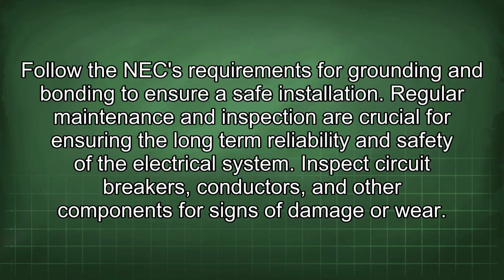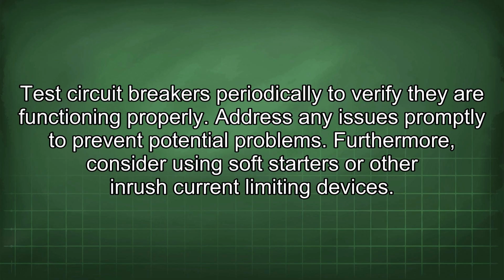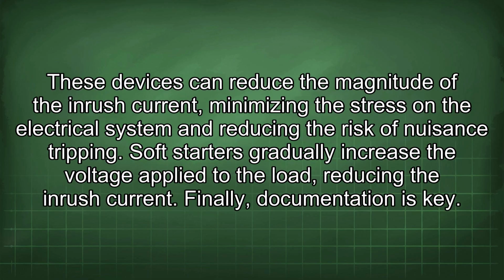Regular maintenance and inspection are crucial for ensuring the long-term reliability and safety of the electrical system. Inspect circuit breakers, conductors, and other components for signs of damage or wear. Test circuit breakers periodically to verify they are functioning properly. Address any issues promptly to prevent potential problems. Furthermore, consider using soft starters or other inrush current limiting devices. These devices can reduce the magnitude of the inrush current, minimizing the stress on the electrical system and reducing the risk of nuisance tripping. Soft starters gradually increase the voltage applied to the load, reducing the inrush current.